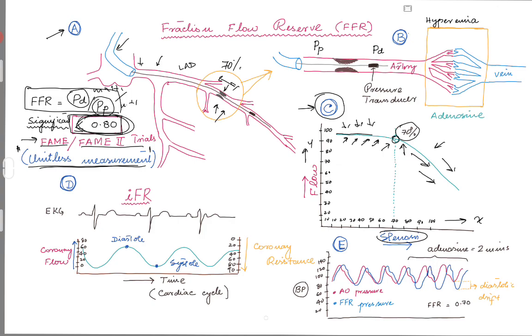With this, we're going to come back to picture B here. This is the catheter in the coronary artery, you see a stenosis here, let's call this about 70% stenosis. And now, as I said, you want to measure the FFR in this patient. As we know, the formula is the pressure distal divided by pressure proximal gives you an FFR. How do we do that? We do that by putting a coronary wire, and the tip of that coronary wire has a piezoelectric crystal that transduces the pressure.